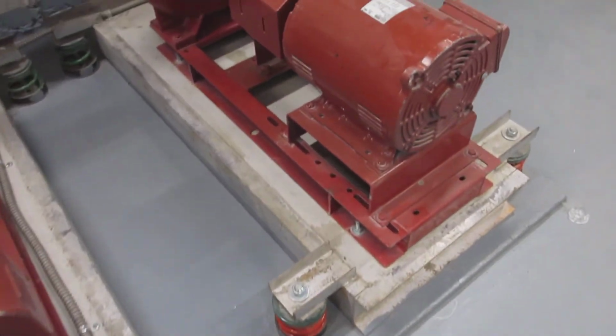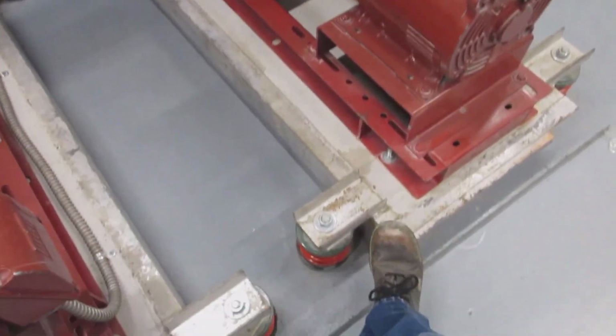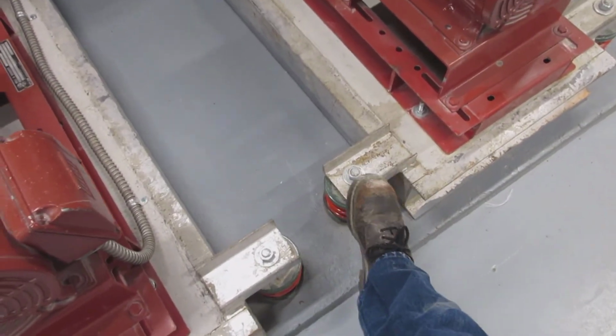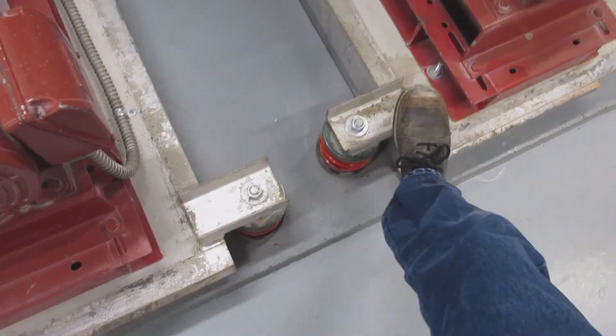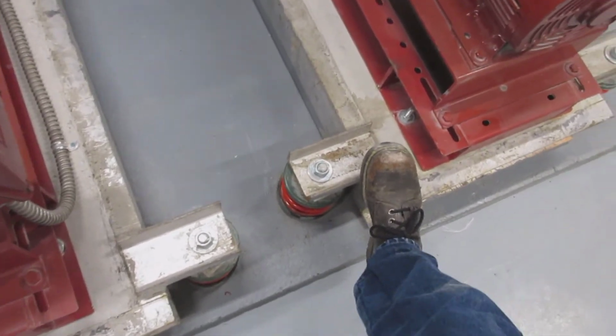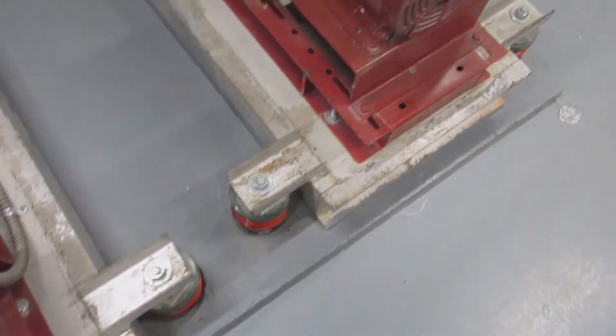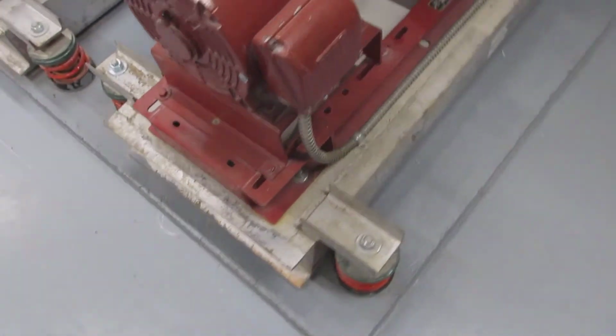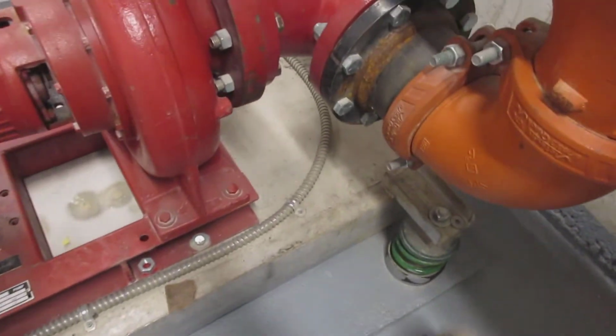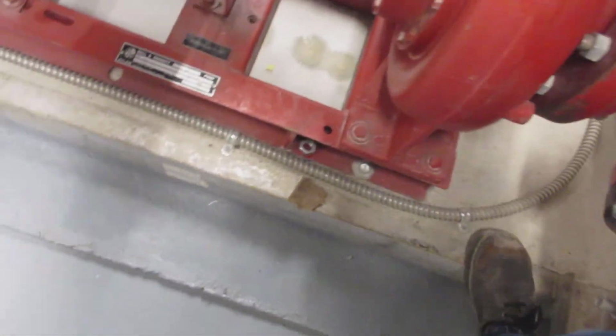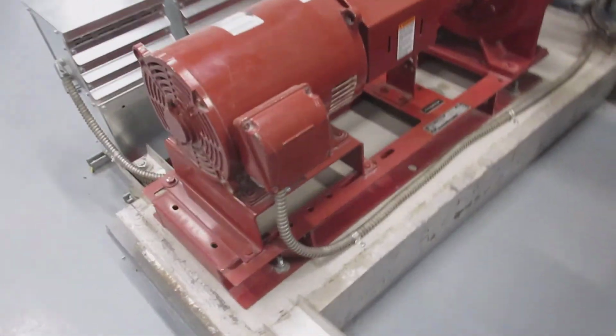I like to use a simple method to determine if something is isolated or floating, where I try to bounce the equipment by pushing on it with my foot. It's a little more difficult to do when holding a camera and trying to take a video, but in this case the pump barely moved, if at all, perhaps due to short-circuiting from debris. I try the opposite corner and have a little more success and get a little bit of movement. In some cases, I've had to stand on the equipment to get it to move.